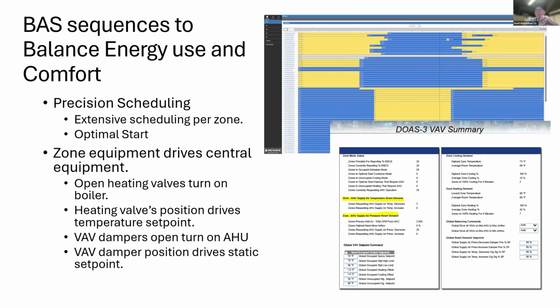We allow the zone equipment to drive the central plant equipment. So we'll schedule the zones, but we don't schedule the central boiler plant or air handlers. We allow the field devices to ask for the equipment that supplies them to turn on. So if we have open heating valves on a fin tube, we'll ask the boiler to run. The heating valve position will then drive the temperature set point. We put that position way up at like 99%. So if the heating valve is doing all it can, it still can't make set point, ask the heating system to increment their set point a little bit. Same with the VAV dampers, they'll turn on the AHU, and if the VAV dampers are wide open, we'll increase static pressure set point.